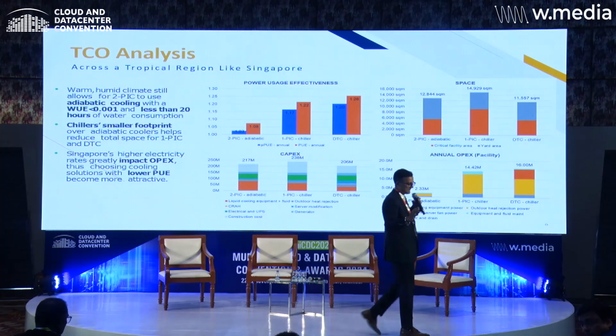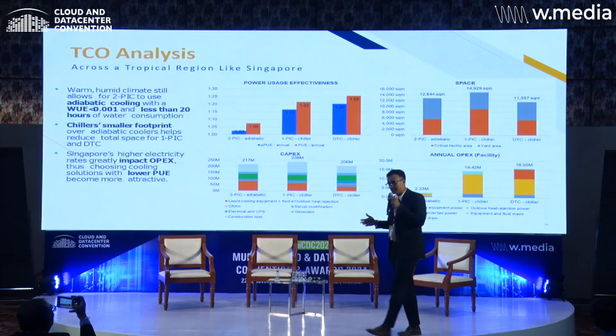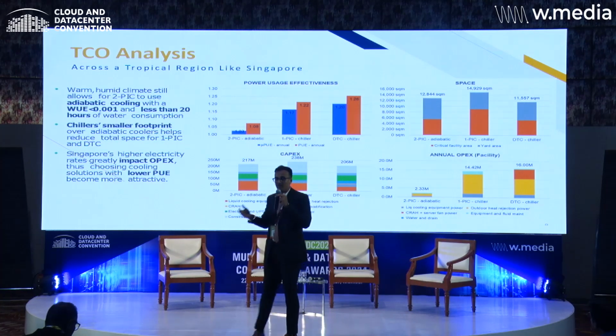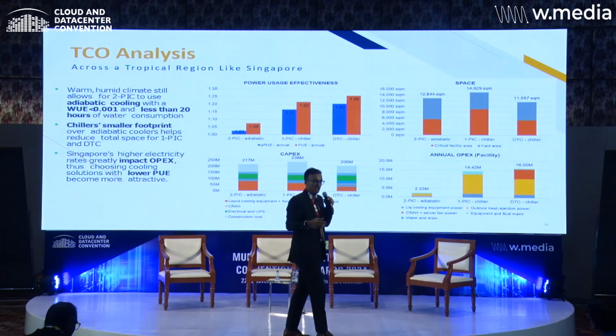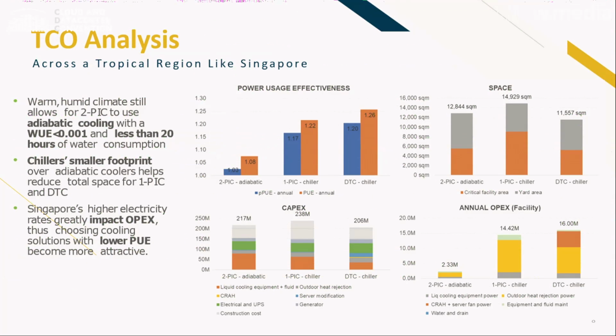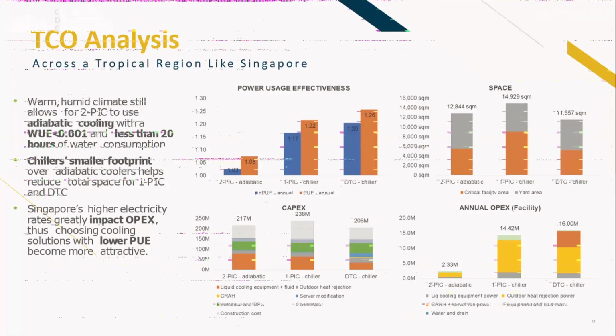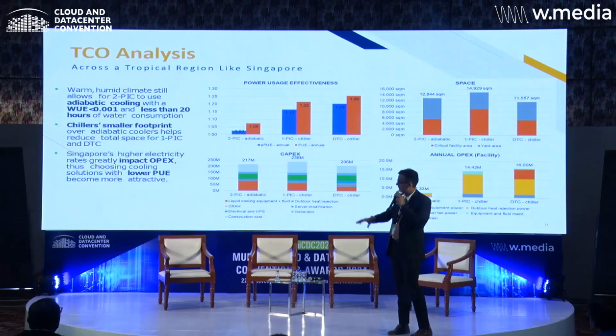Just a total cost analysis of how these systems work. Everyone thinks that two-phase immersion cooling, direct-to-chip, and one-phase are costly compared to air cooling. It is costly in terms of CapEx, but when you take the total cost of the entire project, because you're able to compute more and reject more heat in a smaller space, your total cost is actually not very different. This is an example done by Open Compute for a tropical climate like India. If you see the total cost analysis for two-phase immersion, one-phase, or a chiller system, you will actually see that the CapEx is nearly the same. Plus, you see the OPEX savings are beyond measure.